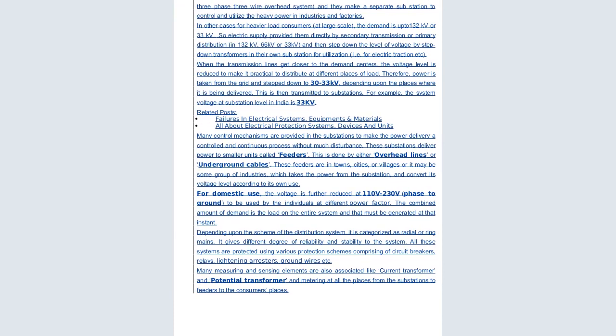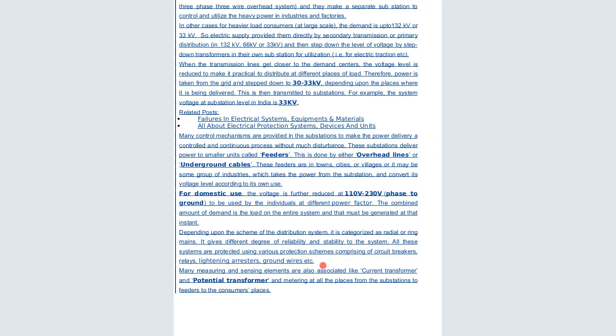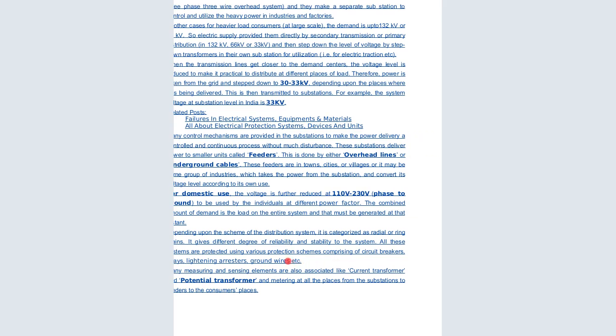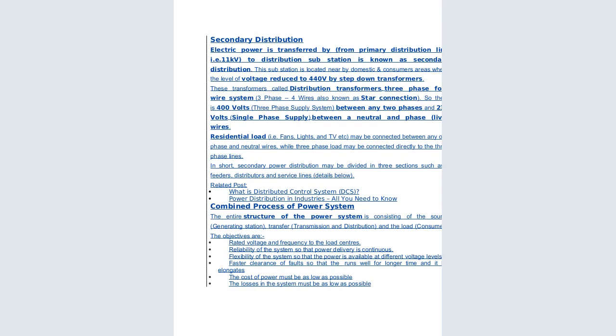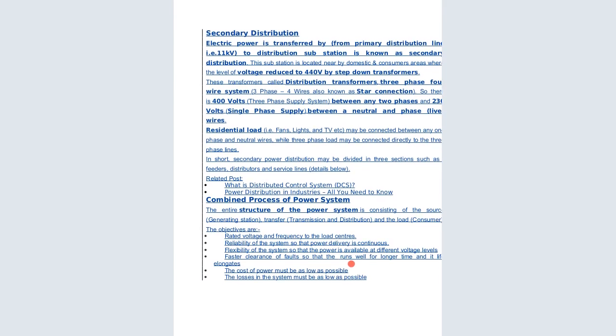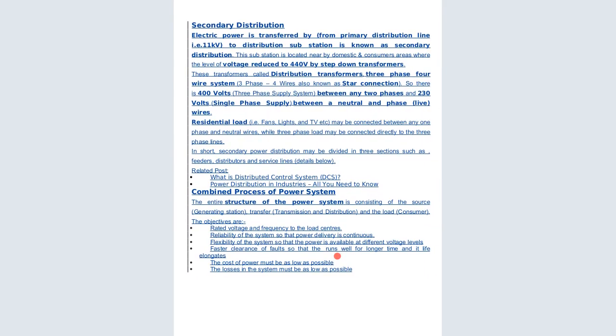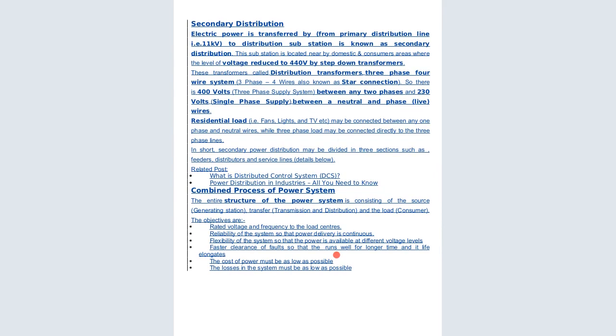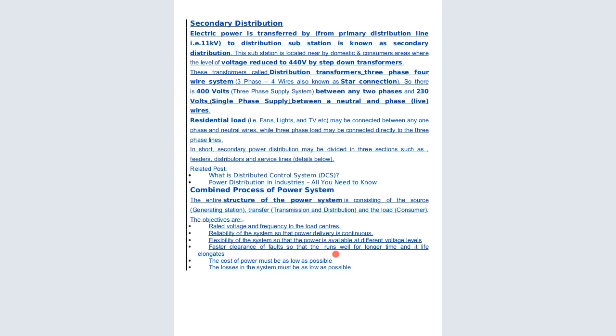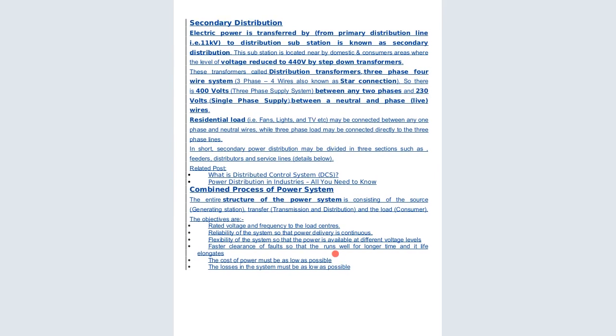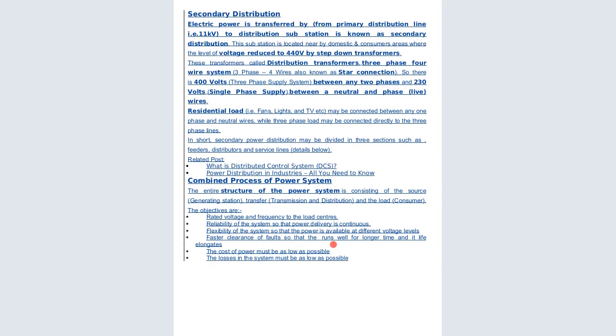So the combined amount of demand and load of the entire system must be generated at the instant. But we measure that using a potential transformer. Secondary distribution. In this, the electric power is transferred from the primary distribution lines to the distribution substation and is known as the secondary distribution. So the substation is located nearby domestic consumer areas, where the level of voltage is reduced by step-down transformers. These transformers, called distribution transformers, are three-phase 4-wire.